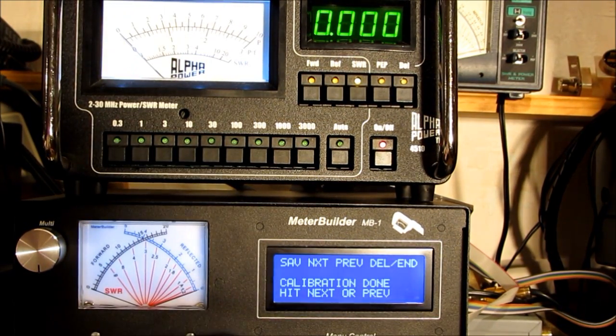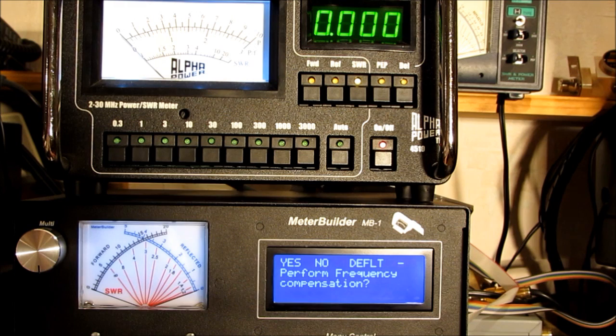After the last calibration point, the meter prompts you to press next. It's basically giving you the option, just in case you jumped ahead to the last calibration point by accident and missed one, to back up to a previous point if needed. If we had simply proceeded to the next step instead, you would not have had that option. We don't need to do that here, so let me just go ahead and hit next.